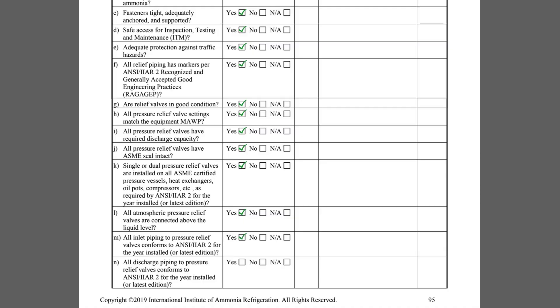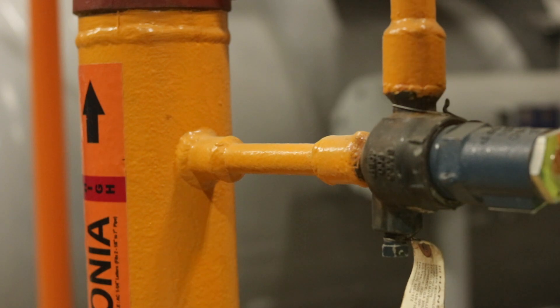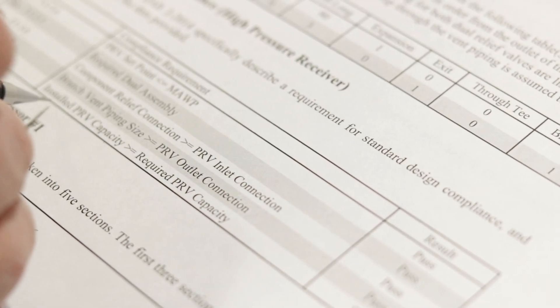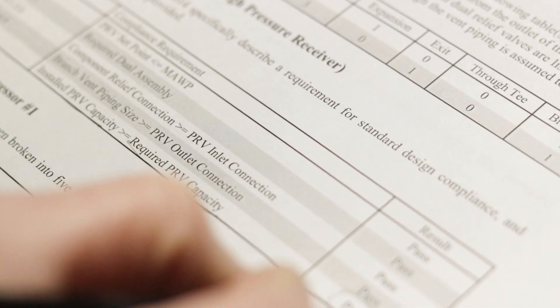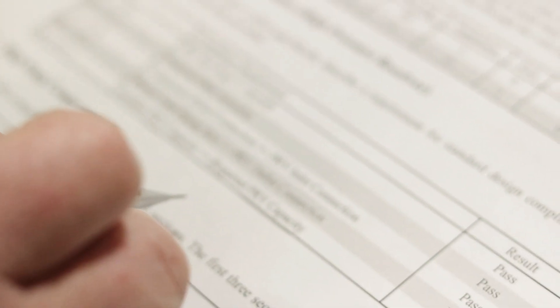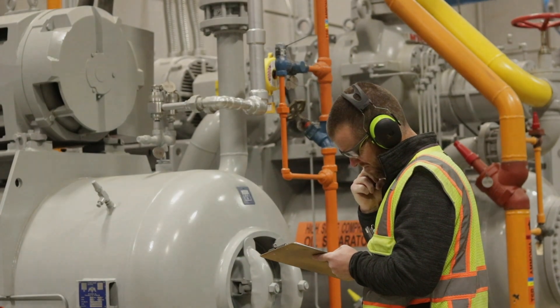Item M inquires if all inlet piping to the pressure relief valves conforms to the edition of IIAR Standard 2 that was effective when the relief system was installed. It is beyond the scope of this video to provide a full explanation of the inlet piping requirements, but the inspector must verify that relief system calculations are available and that egregious deficiencies, such as an expansion into the relief valve inlet connection, are not present.